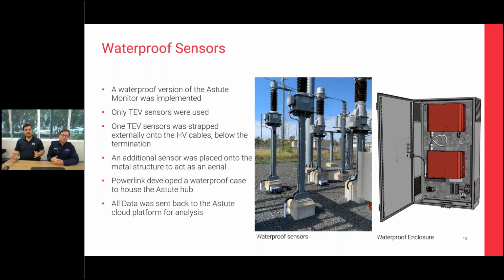One of the next things we did—these were restricted zones because of high levels of oil, acetylene in the oil, and some other tests, and they didn't want people having to go and inspect or test them physically. So all of the data came back to us in the cloud, allowing us to sit in, hopefully, air-conditioned offices and analyze all of the data remotely without putting any safety implications on staff, which had been one of the biggest hold-ups for further oil analysis.